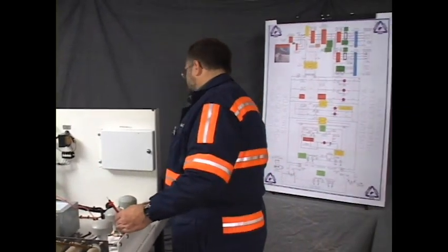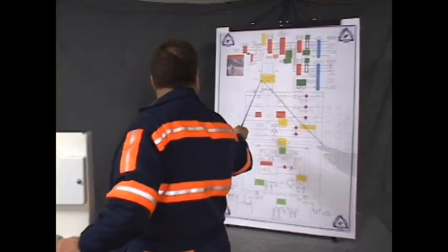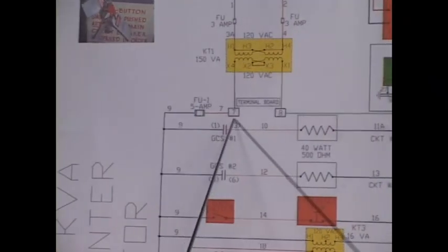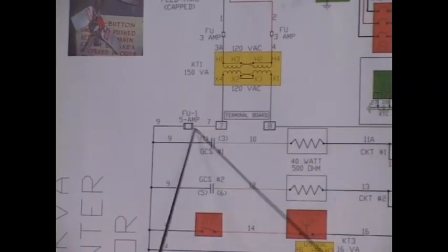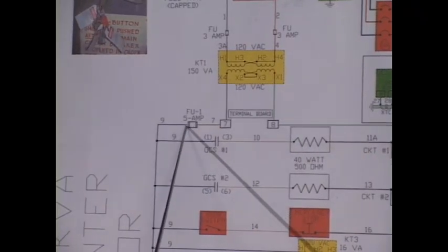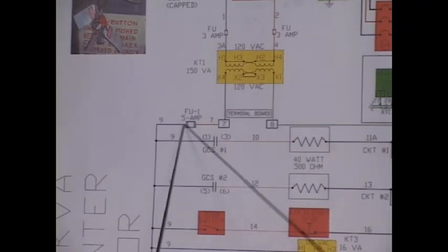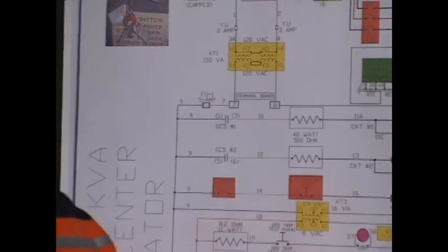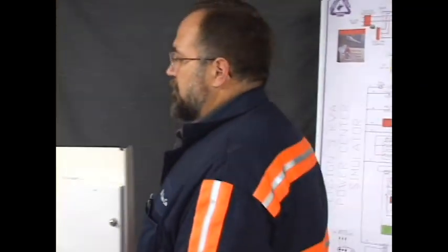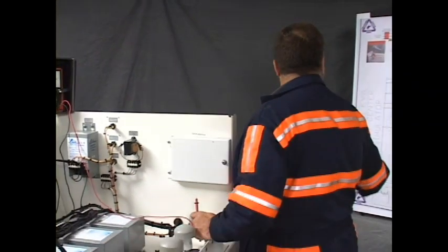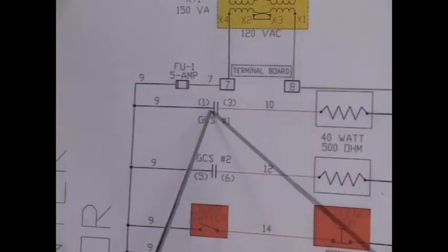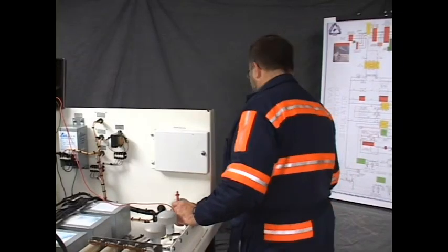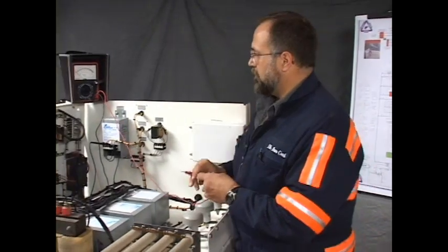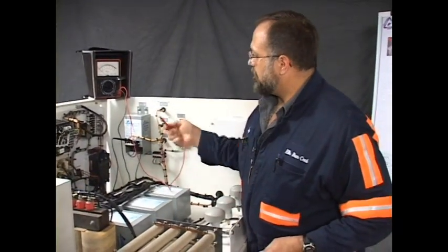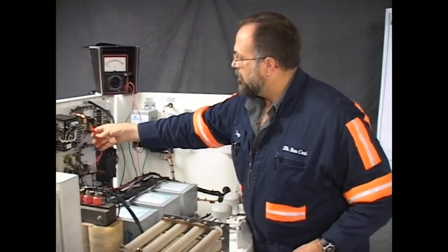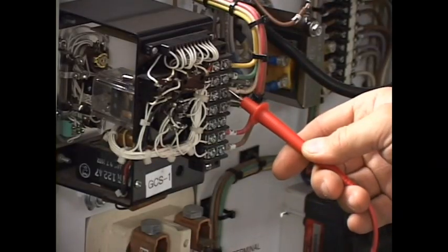On the drawing, what we've checked so far, we attach one probe here, read to the terminal board. From the terminal board, we read to the line side of the fuse. Then we read through the fuse, always checking back to here. So we're at wire number 9, and everything appears to be intact. The next point that you can access wire number 9 is on GCS1, terminal 1 of GCS1. Wire number 9 is a white wire, and it's labeled as wire 9, and it's easy to find right here.